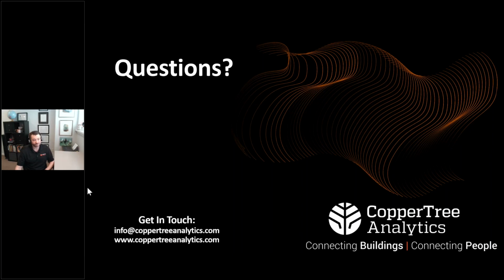Can you hear me? Is it coming through? Yep, I can. Just a quick question about some of the Copper Tree devices. We do have Copper Tree in our organization, and we're using the Copper Cube product, which I guess is now obsolete. My question was, the K-Link doesn't do data storage for trend logs the same way that the Cube does. That's what I've been told. Is that correct? That is correct. And I've also been told there's not really a direct replacement for the Copper Cube. That's also correct? Well, that's not correct.